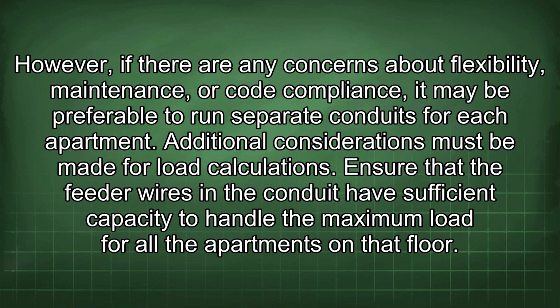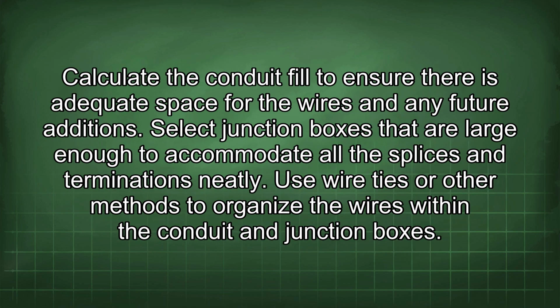Ensure that the feeder wires in the conduit have sufficient capacity to handle the maximum load for all the apartments on that floor. Calculate the conduit fill to ensure there is adequate space for the wires and any future additions. Select junction boxes that are large enough to accommodate all the splices and terminations neatly. Use wire ties or other methods to organize the wires within the conduit and junction boxes.